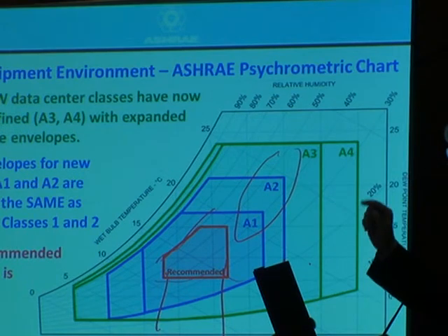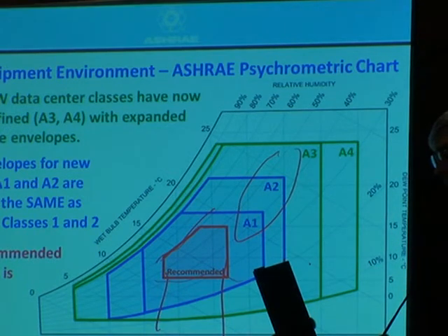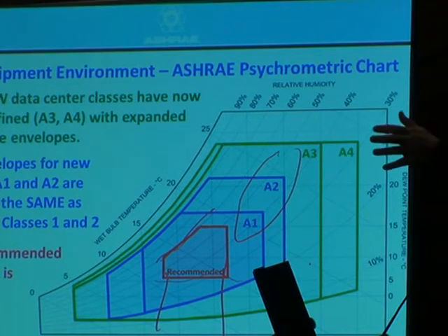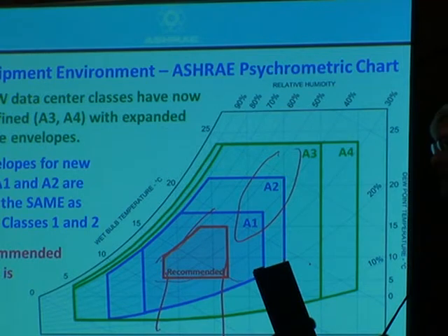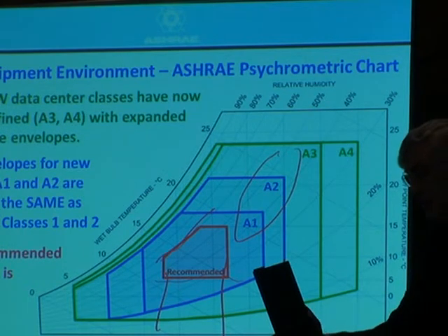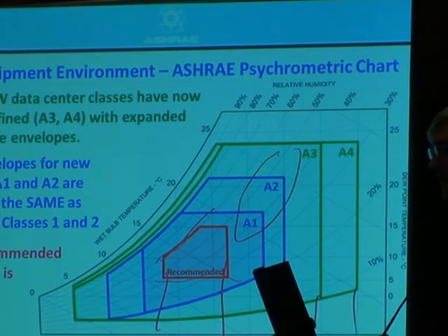So the push has been from customers around the world to ask the IT manufacturers to make equipment to higher temperatures. Again, if Moscow is 37 in the summer, you would ask maybe why don't the IT manufacturers make equipment to 40 C? If you had that, maybe I wouldn't need air conditioning. So we produced these two new classes, 40 and 45. That is real hot.